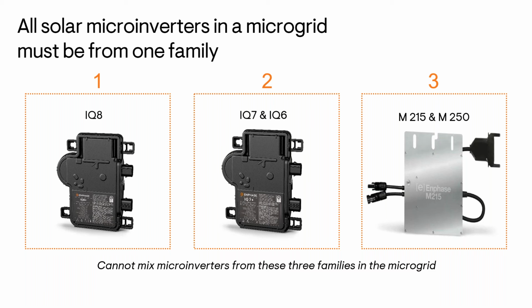So another question that you might get is, I've got a small IQ7 system, I want to increase the size of my system and have sunlight backup. If that's the case, then they would actually have to replace all their IQ7 microinverters with IQ8s for a sunlight backup configuration. My advice there is to recommend just keeping the IQ7s on the solar array, add some solar panels with more IQ7s, and then use the money you would have spent on replacing the IQ7s on a battery instead. That customer is going to have a much better backup power system.